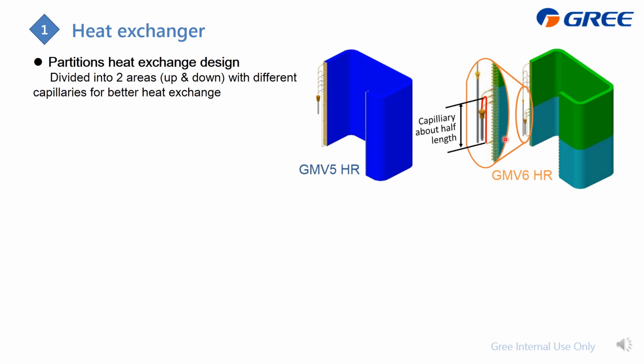The benefit compared with GMV5 is this: this is the distributor, and in heating you need to distribute the liquid refrigerant from here to the furthest passes. This is actually a small size tube, and for mass production, it is not easy to control this length. If we cannot ensure this length, the distribution will not be even. Uneven distribution in heating means ice can easily form on the surface of the outdoor heat exchanger, which means the heating performance will be poor.